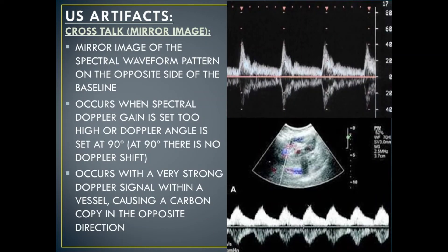The next type of ultrasound Doppler artifact is known as crosstalk, also called mirror image. This is a mirror image of the spectral waveform pattern, which shows up on the opposite side of the baseline. This occurs when the spectral Doppler gain is set too high, or the Doppler angle is set at 90 degrees. At 90 degrees, there is no Doppler shift. This also occurs with a very strong Doppler signal within a vessel, causing a carbon copy in the opposite direction.